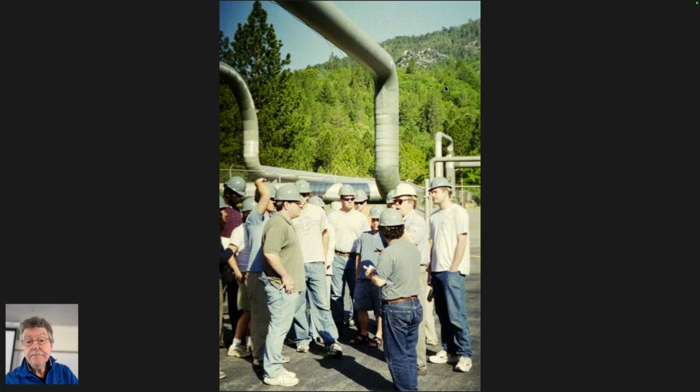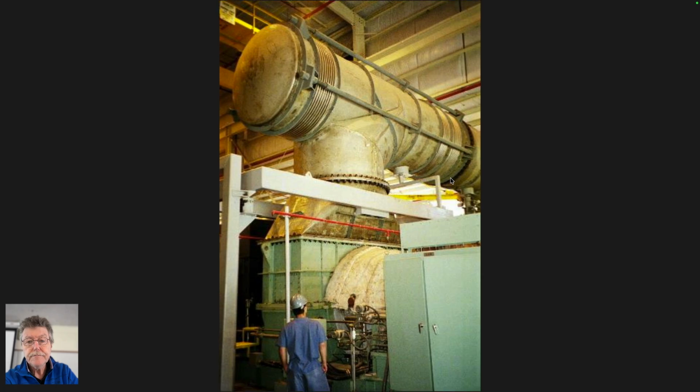Pipes with lots of bends in them, so that when they thermally expand and contract, there's lots of leeway in this elbow junction for it to expand this way and that without straining the pipes. Pipes that go across roadways like this to be able to expand and contract.